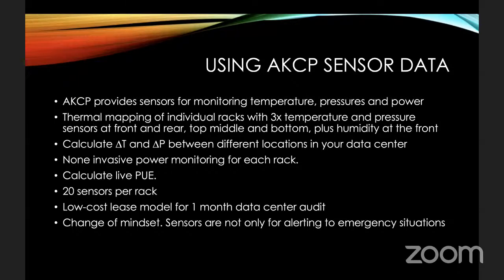So 20 sensors per rack, plus we will monitor the CRAC. We will monitor the airflow of the CRAC. And potentially in a 100 rack data center, you could be talking then about 20,000 data points, if we include all of the other ancillary monitoring that we're also going to include with the CRAC units and the air handlers. So with this amount of data, we can then create a CFD model that is constrained not by assumptions, not based on the manufacturer's specifications, but based on real world sensor data. So rather than the input to that CFD model being this CRAC has a certain number of BTUs, this rack is consuming a certain number of kilowatts, and we're assuming that it's at this temperature, we are constraining that CFD model based on real, actual, live sensor data.